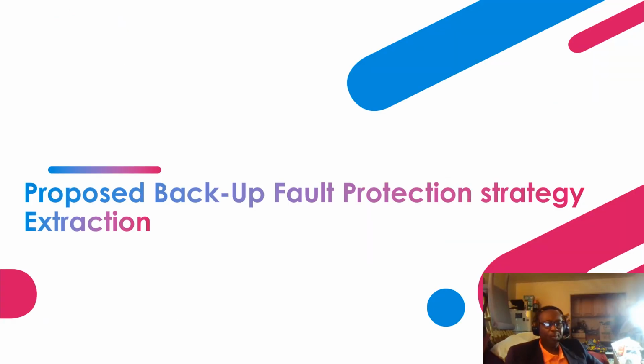Next, we'll talk about the proposed backup fault protection strategy. I have a main protection scheme, and definitely I will need a backup protection scheme to come into place when the main protection scheme fails. So I'm utilizing the AC side circuit breaker as a backup protection. As I indicated, this AC side circuit breaker usually takes about 20 to 80 milliseconds to implement the tripping of the DC grid.